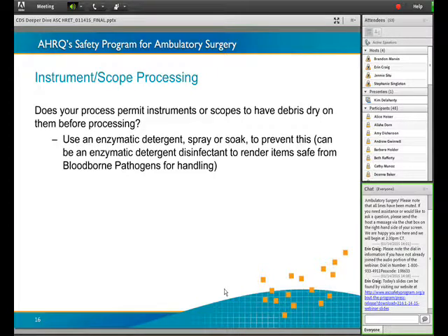Hinged instruments can go through the instrument washer and still have blood in the hinges, so that's another reason why enzymatic cleaning is so important. The instrument must be physically taken apart and scrubbed. Otherwise, the hinge will be open during surgery and dry flakes of organic material may fall out into the sterile field. And we've seen that happen. We've had unusual occurrence reports on this specific issue.